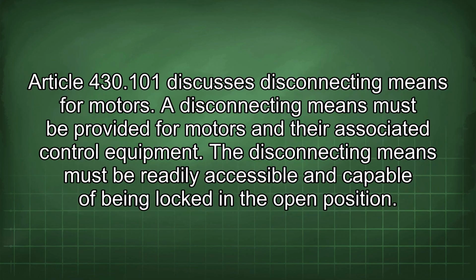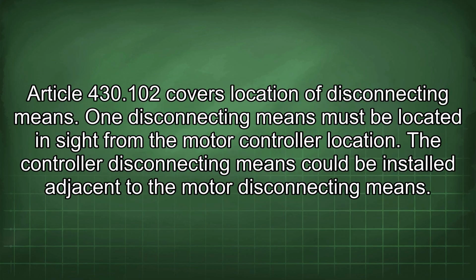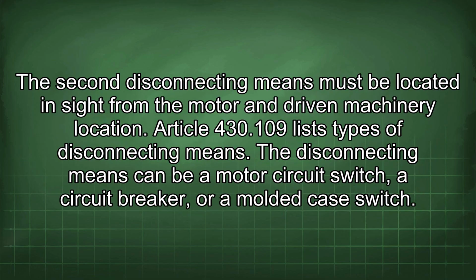Article 430.101 discusses disconnecting means for motors. A disconnecting means must be provided for motors and their associated control equipment. The disconnecting means must be readily accessible and capable of being locked in the open position. Article 430.102 covers location of disconnecting means. One disconnecting means must be located in sight from the motor controller location. The controller disconnecting means could be installed adjacent to the motor disconnecting means. The second disconnecting means must be located in sight from the motor and driven machinery location.